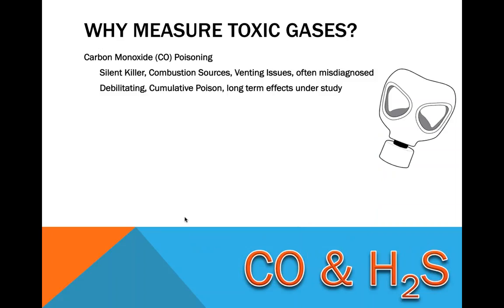Carbon monoxide poisoning is a big factor. CO is called the silent killer because you cannot detect it with any human senses. It can come from combustion sources, of which there's lots around in all our activities of daily life. It can be introduced into a space through venting issues, and actually be caused by venting issues when the airflow is not correct through a system.